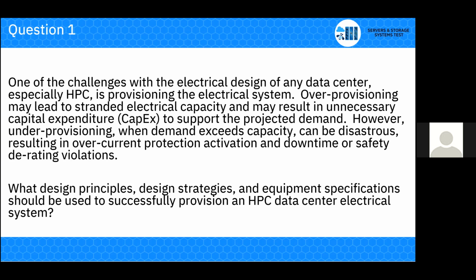So, Ethan? I'm more on the implementation end, but really understanding what the loads are, how the loads operate, trying to figure out what factors people have included in their information. Make sure people haven't oversized their requirements because they want a safety factor, and then the engineer on top of that puts in a safety factor too. So make sure everybody's aware of the safety factors being built into the system. Understand the capabilities of the equipment supplied. A good example is 80% rated breakers versus 100% rated breakers.